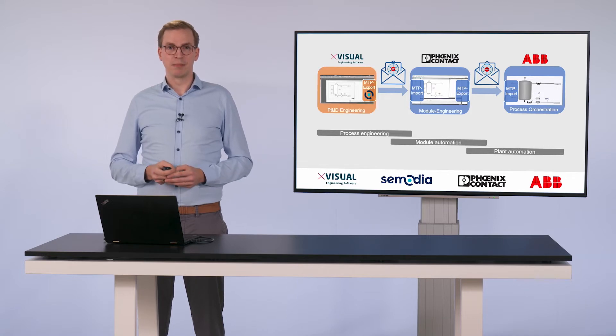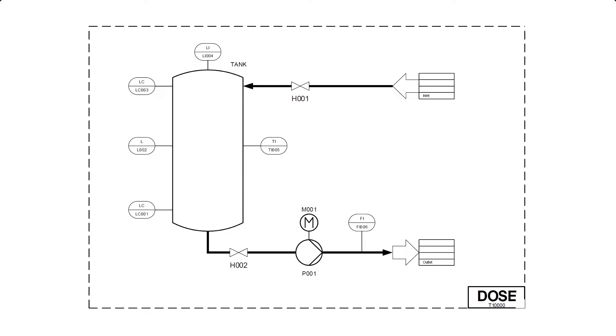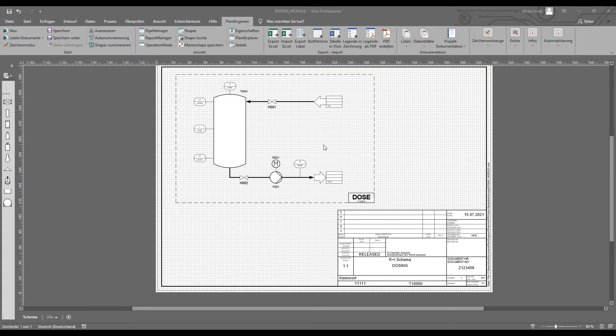Let's start with P&ID engineering. Here we see the P&ID for our dosing module. The module has a container, an inlet and outlet with valves, a pump and relevant sensors to measure various process values. Since the P&ID of a module is prepared in process engineering anyway, it's a good idea to use the P&ID information to create an MTP in order to reduce the workload. I would like to present the process for adjusting the P&ID and MTP export in Plant Engineer in more detail. Plant Engineer is a P&ID software based on Microsoft Visio, with a user interface that integrates seamlessly into the Visio interface. The P&ID is not just a simple graphic drawing, but rather a representation of a complex informational model that describes the P&ID in the background, supplemented by data that can be used to generate the MTP.